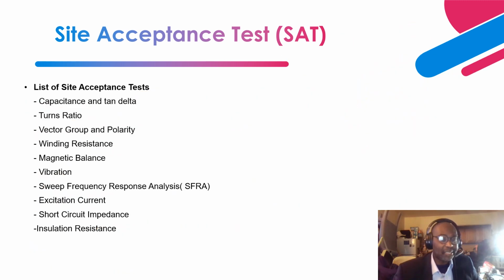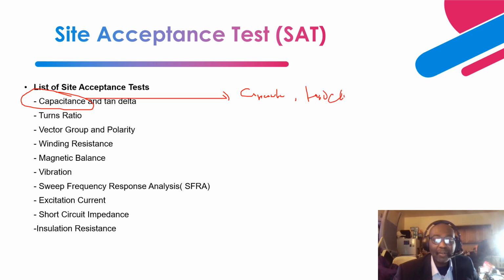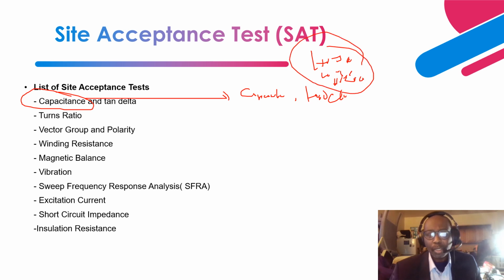So now let's talk about the testing, right? First one is a capacitance test. Capacitance testing is done in addition to the tan delta test. Like I told you, the active component of the power transformer, that is the insulation system, the thermally upgraded paper, the solid insulation and the liquid insulation, are all arranged in such a way that they create a capacitance network. We have a high voltage to ground capacitance, low voltage to ground capacitance, and high voltage to low voltage capacitance. So basically, the arrangement tells you the geometrical configuration of the active component, based on the capacitance that this insulation system, the conductor and the ground plane form.